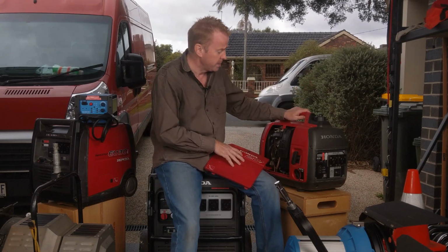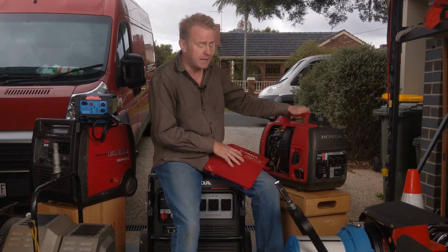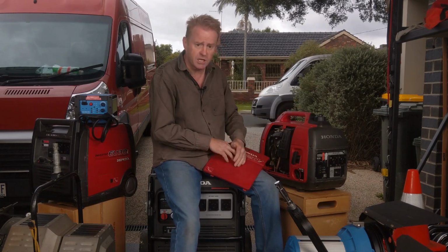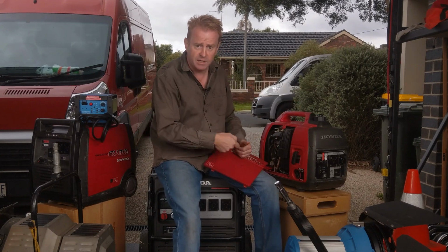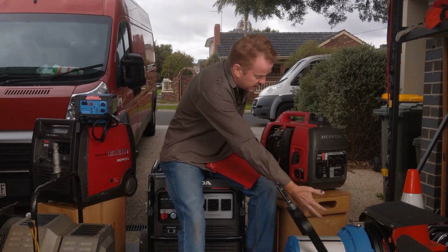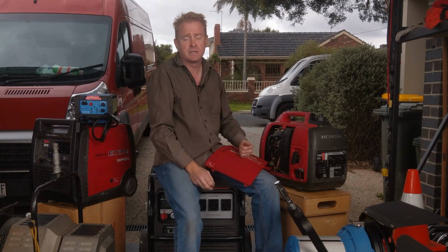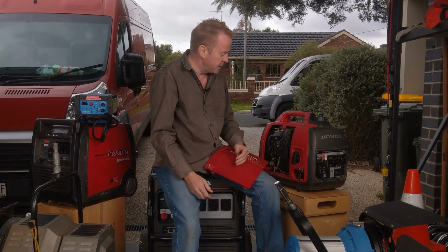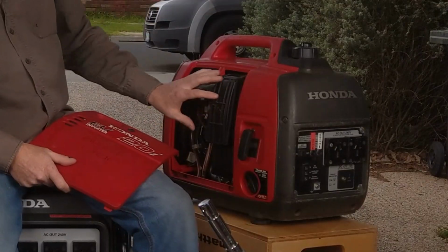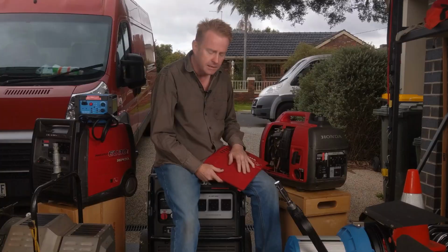So that doesn't work. The next problem I have is people running these on beaches. They basically just go out, put the generator on the sand and turn it on, and then this thing basically sucks sand in through its air intakes and stops working. And I've had a few rentals where I've opened up the air filter and it's just full of sand.